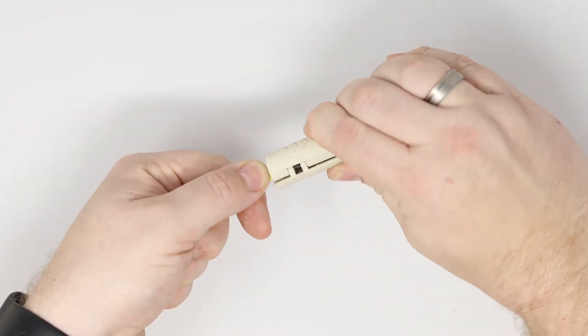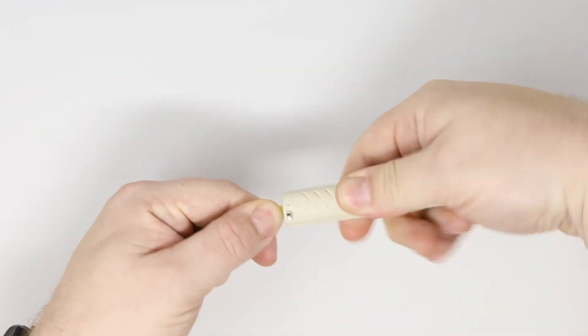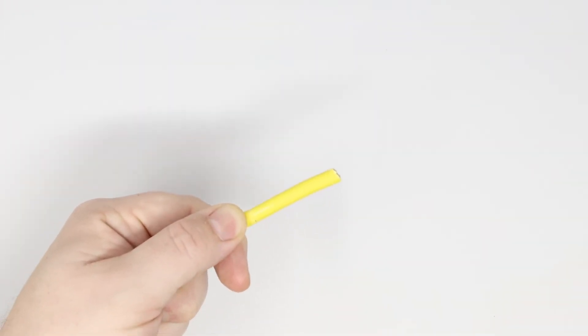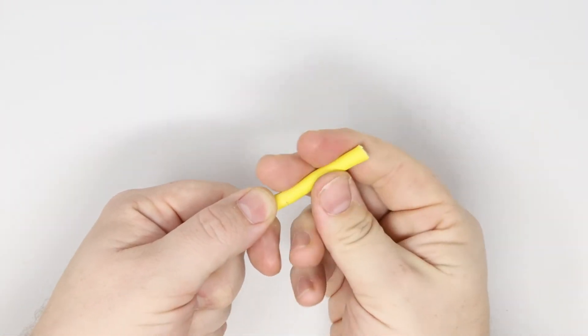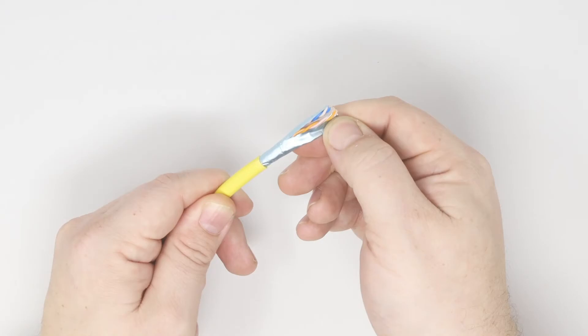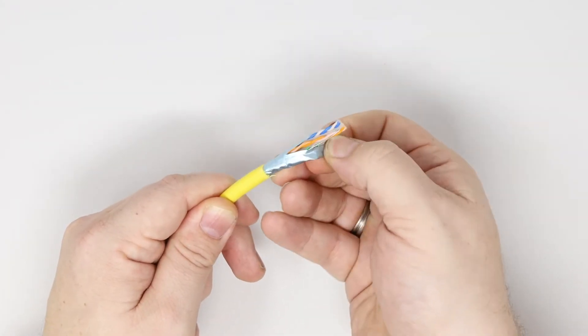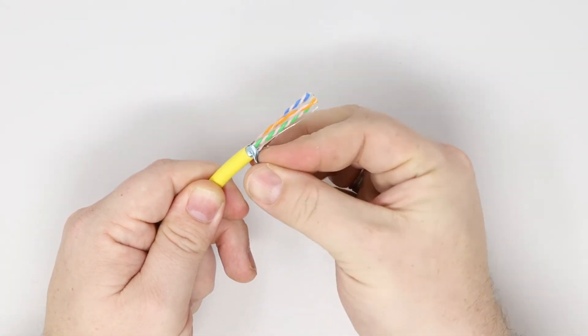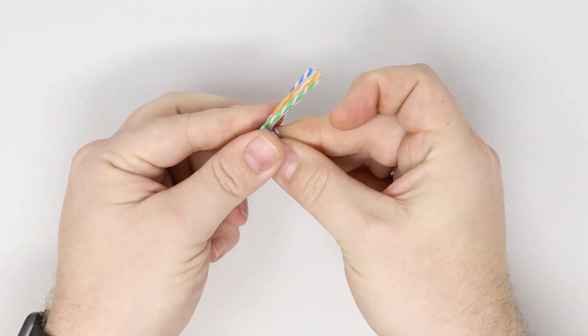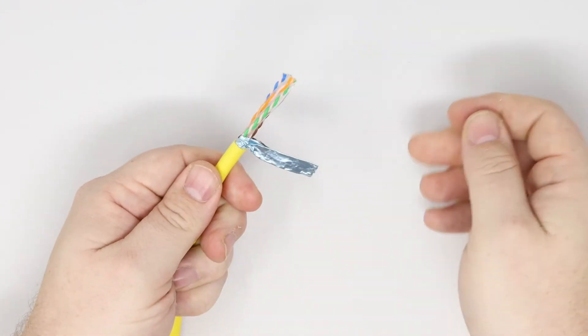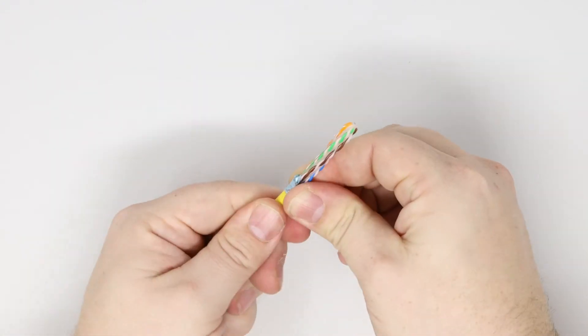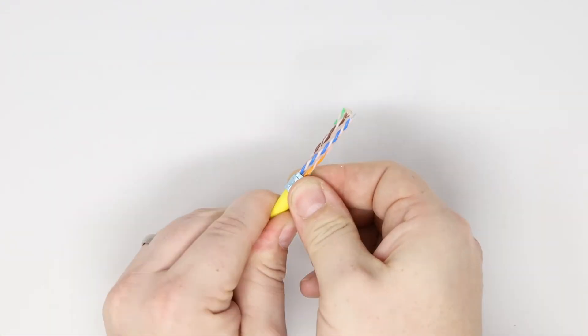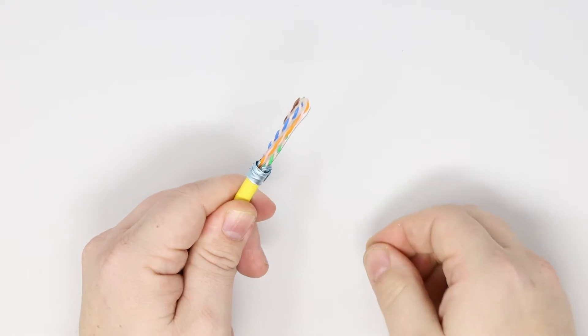Take your cable jacket stripper and remove approximately 25mm of the jacket. Carefully unfold the cable shield. Fold the foil in half and wrap around the cable jacket as shown, ensuring a 360 degree wrap is achieved.